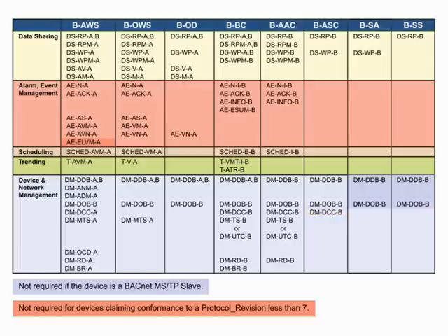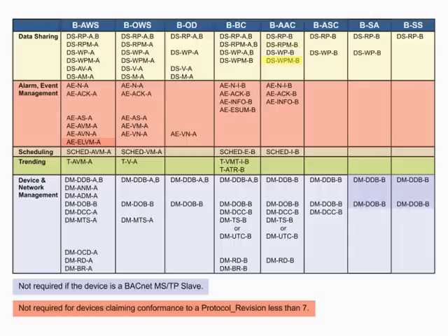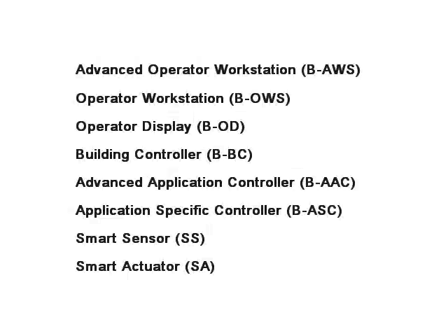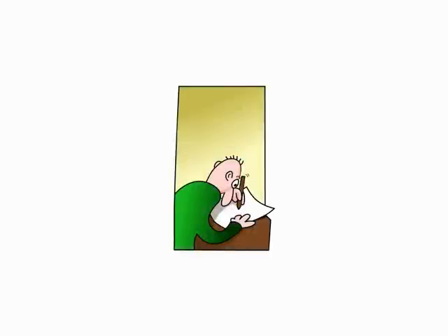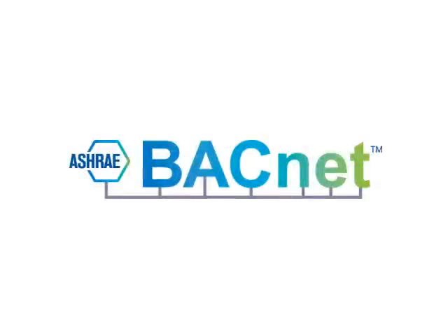However, there is no requirement for the B-ASC to support alarming, scheduling, or trending. The Advanced Application Controller provides additional functionality over the B-ASC by providing read property multiple and write property multiple. A device profile is a short way to classify a device, but it only defines a minimal set of BIBs. If you want to learn all the BIBs a device has, you study its Protocol Implementation Conformance Statement, or PICS. We will learn about PICS in our next video in this series.